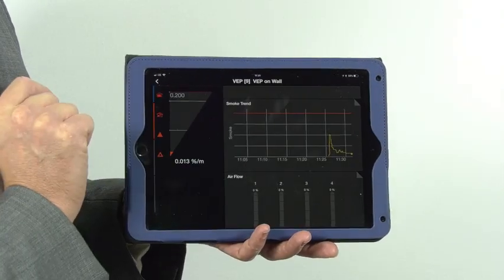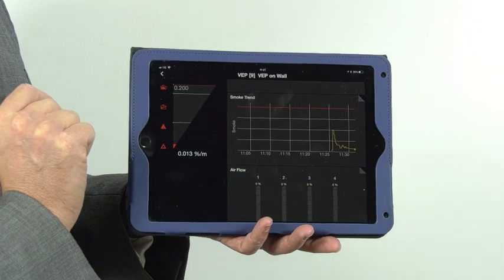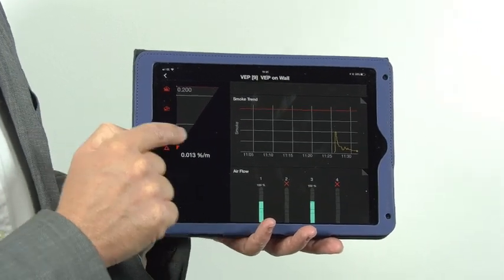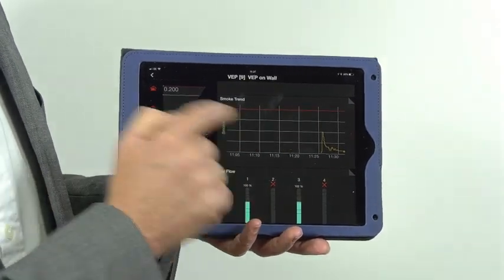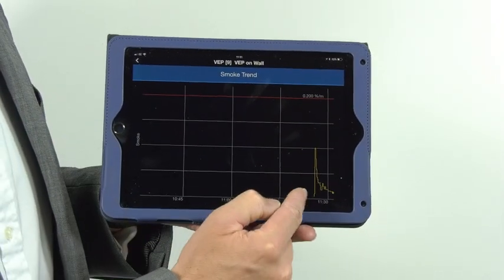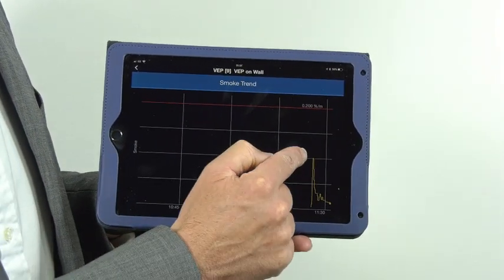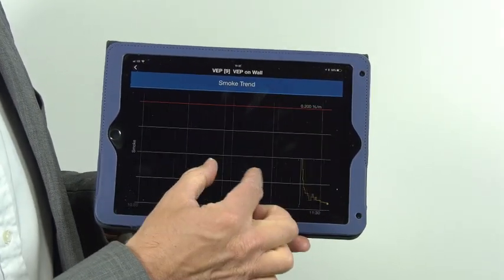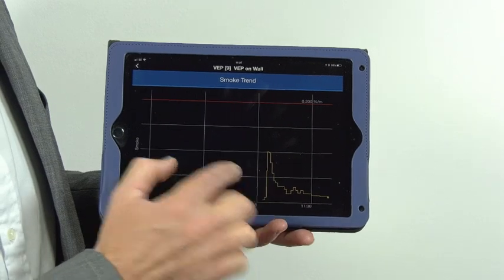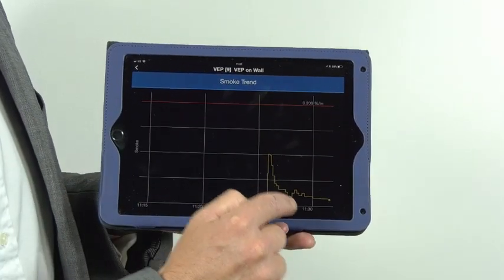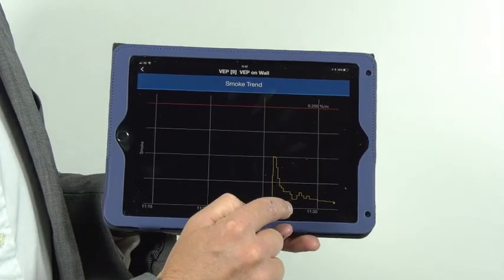If I move into that screen, we can see that alarm has now cleared. We can also see through the smoke trace that the alarm peaked at a certain point. We can zoom in and get more detail, but the alarm has now dropped back off.